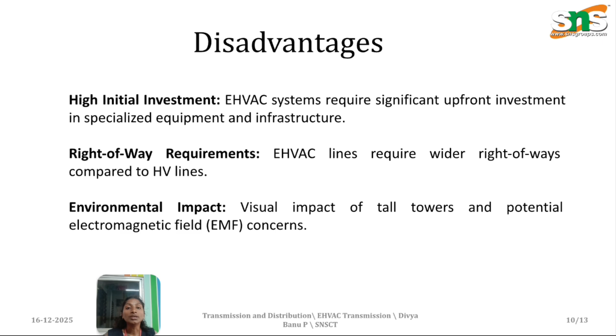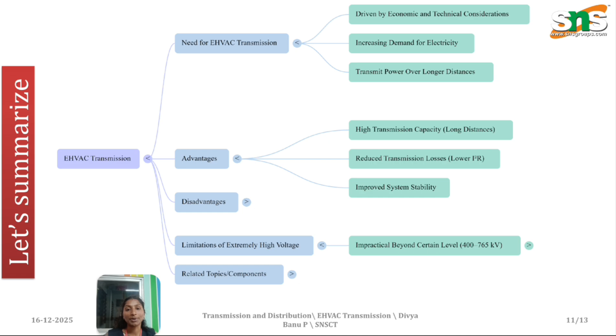Summarizing today's video on extra high voltage AC transmission systems: the need for extra high voltage AC transmission is driven by economic and technical considerations, increasing demand for electricity, and the need to transmit power over long distances. The advantages are high transmission capacity, reduced transmission losses and improved system stability. Coming to limitations, it is impractical beyond a certain level, like 400 to 765 kilovolts - it is not practical and cannot be used.